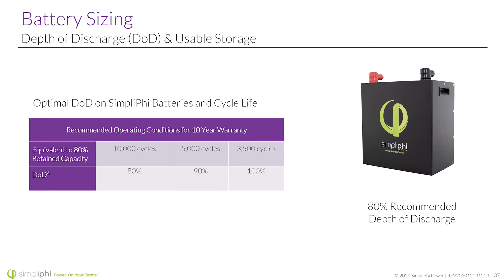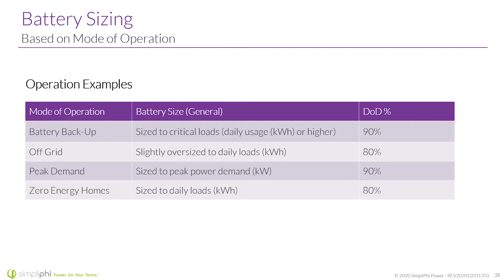That's where you can base your depth of discharge, beyond the warranty, off your mode of operation. Say you've got an off-grid system - that customer will charge and discharge daily, so to maximize the battery's lifespan beyond the warranty period, we likely want to stick with something like 80% depth of discharge, using 80% of the battery's usable capacity. But in a battery backup situation, where it's just for when the power goes out and that doesn't happen often, it might make more sense to go with 90 or 100% depth of discharge.